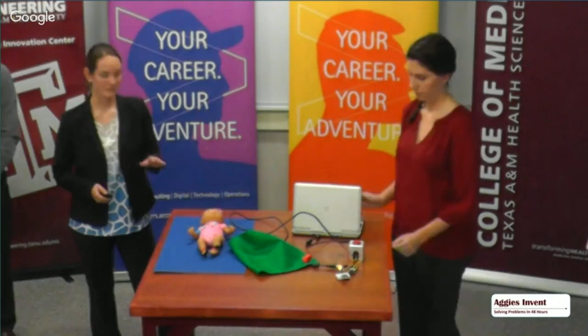Then the button is going to be next to the incubator. The nurse will press the button before she reaches in and changes the baby's diaper or checks the baby's heart, anything that she would normally do. That button works for a specified amount of time—we set it up for 10 seconds right here. So as long as it's lit up, any alarms that are set off will not occur.